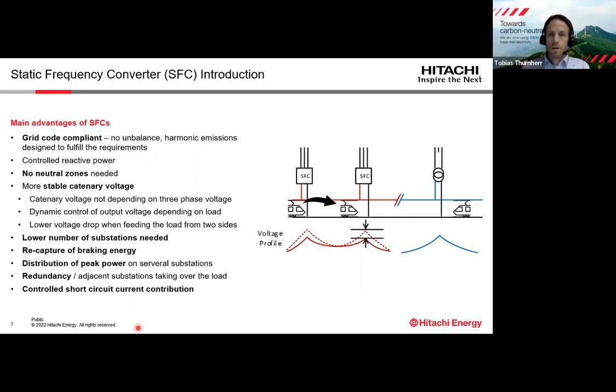So, grid code compliance: the SFC equally distributes the load on all three phases, so we don't have unbalance. The harmonic emissions on the three-phase side are designed to fulfill the requirements. So basically, we get the project-specific limitations, and then we design the SFC to fulfill these limitations. And we can also control the reactive power on the three-phase feeding grid side. Typically, the SFCs operate at unity power factor, but they can also contribute to voltage control and reactive power compensation. And we have customers that use this feature to stabilize the voltage of the three-phase grid they are connected to.